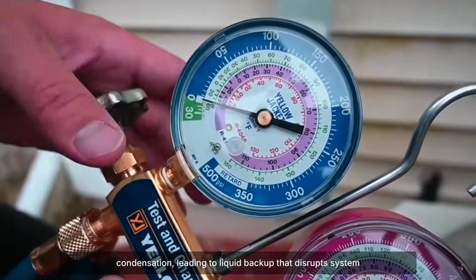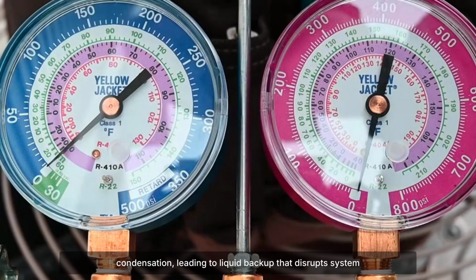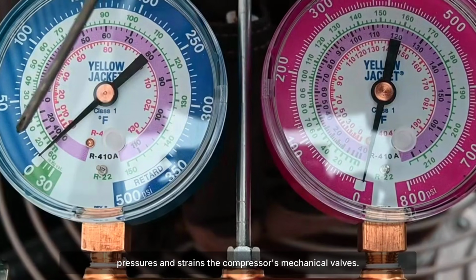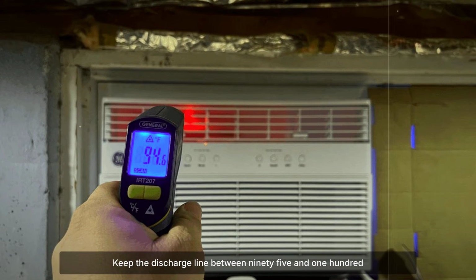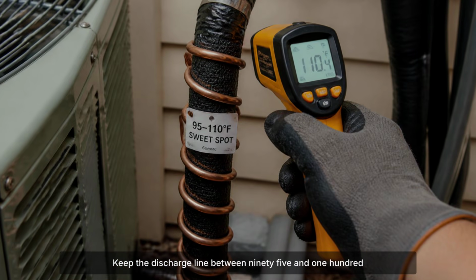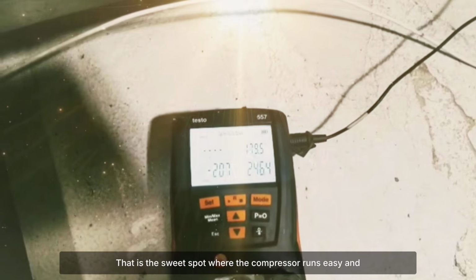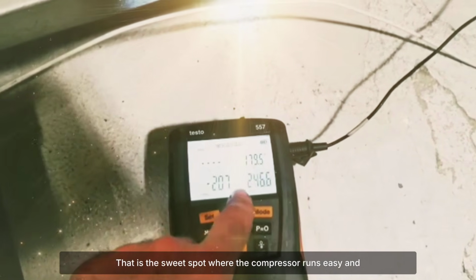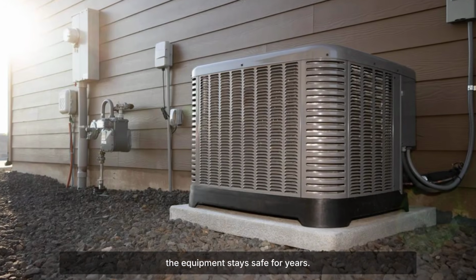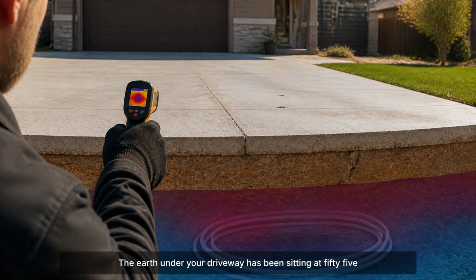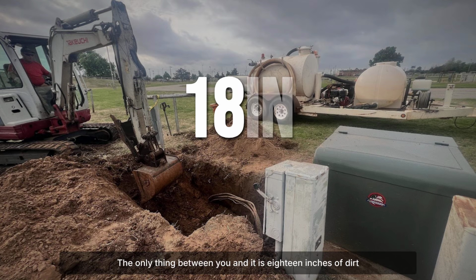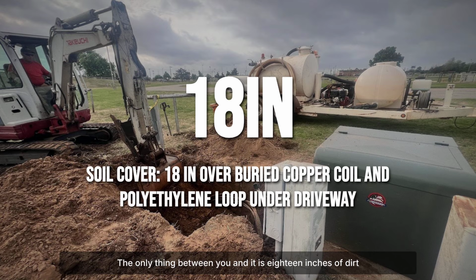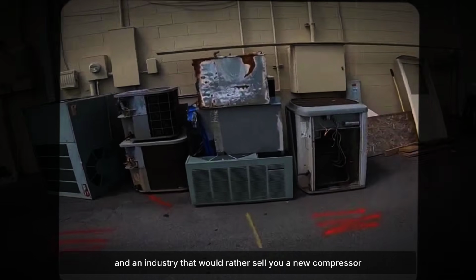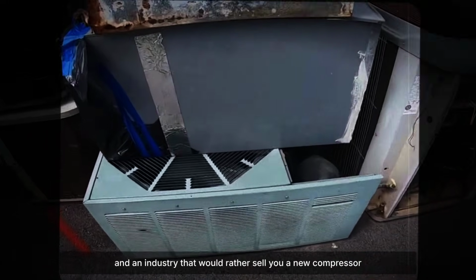Overcooling the discharge gas can cause premature condensation, leading to liquid backup that disrupts system pressures and strains the compressor's mechanical valves. Keep the discharge line between 95 and 110 degrees. That is the sweet spot, where the compressor runs easy and the equipment stays safe for years. The earth under your driveway has been sitting at 55 degrees this entire time. The only thing between you and it is 18 inches of dirt and an industry that would rather sell you a new compressor every 12 years.